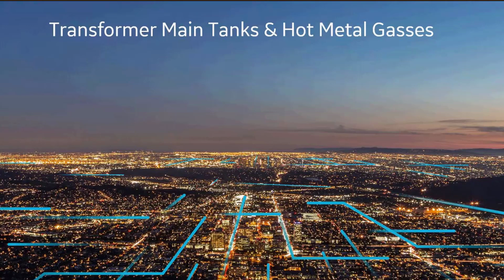When you break this thing down, I always look at it from the standpoint of a lot of paper—to me, that's winding. A little paper could be transformer leads that are wrapped with kraft paper, or it could be some outer winding kind of issues you might have. Or what I always use the term—I guess I heard it somewhere years ago, and I'm still using it—bare metal. So when I think of bare metal, I think of contacts or connections, one of those two.